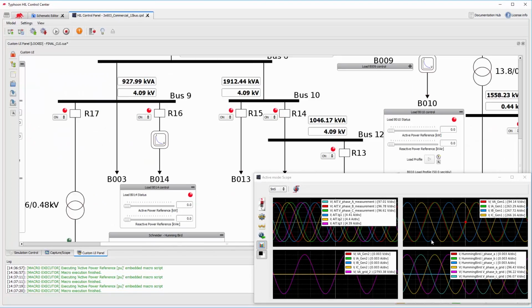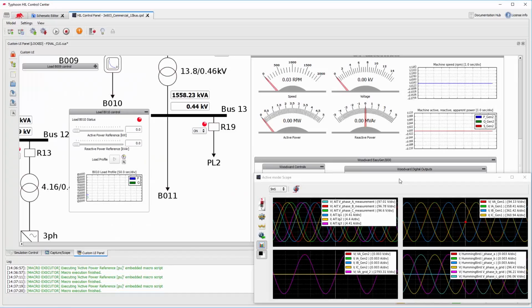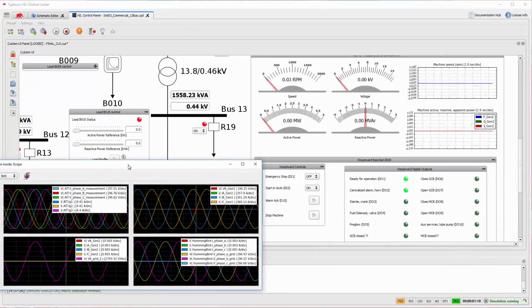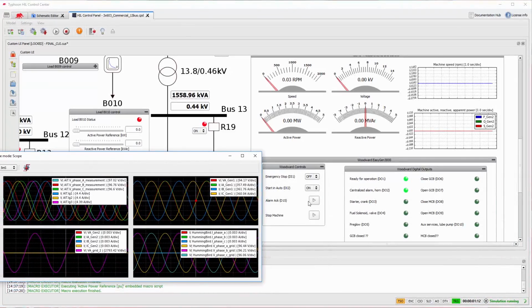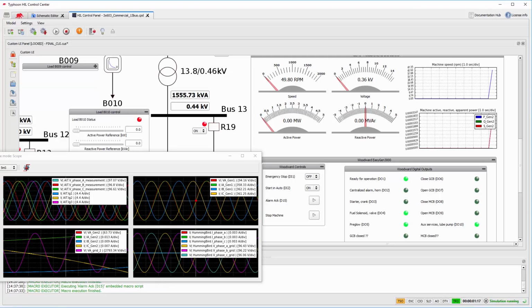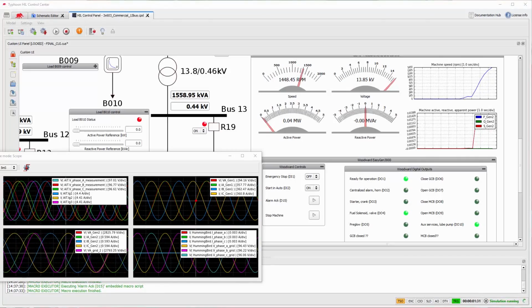The same startup process is automated by the Woodward controller for the Genset 2. To start the Woodward controller, we need to clear its alarm register, and if the grid is under nominal conditions, no alarms will appear and the Genset will start. We can observe the speed ramping up with the tracegraph widget. Once the speed reaches nominal state, the controller enters the synchronization mode.